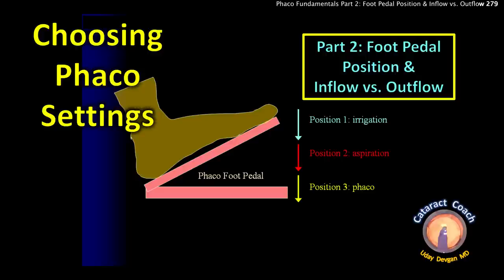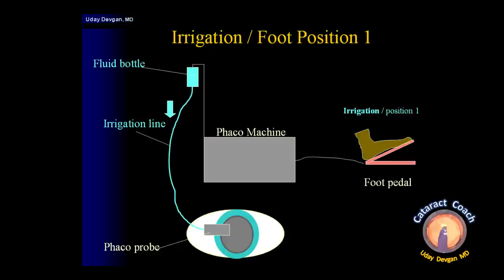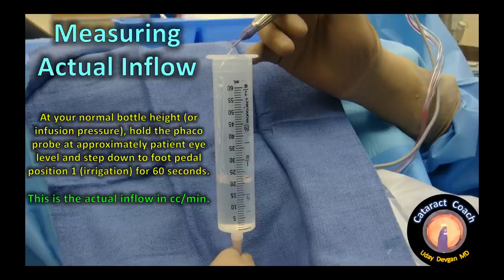CataractCoach.com — choosing phaco settings, part two: foot pedal position and inflow versus outflow balance. The foot pedal is very important because it's the direct way that the surgeon interacts with the phaco machine — that's your control. Starting with the basics: foot pedal position one is irrigation, which allows the inflow of fluid from the hanging balanced salt solution bottle, or from the infusion bag on machines with forced infusion, to bring fluid into the eye.